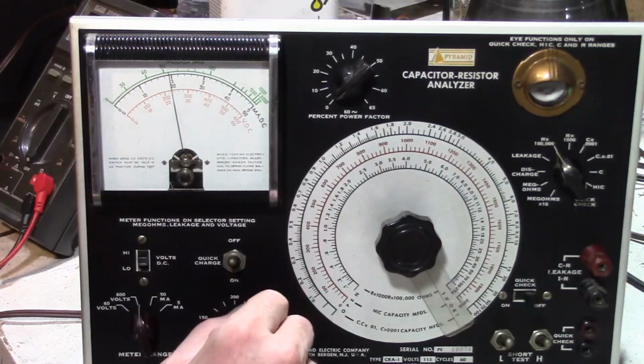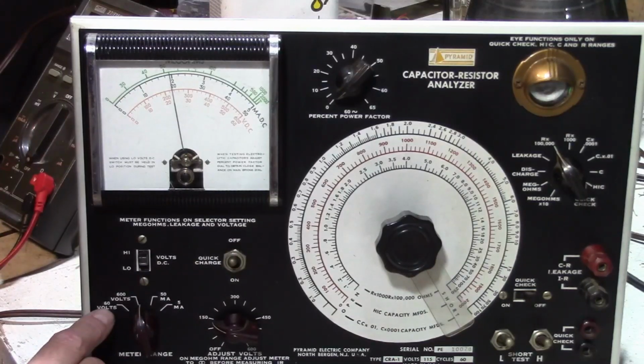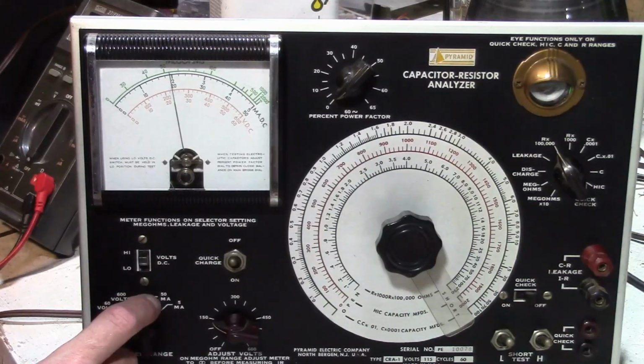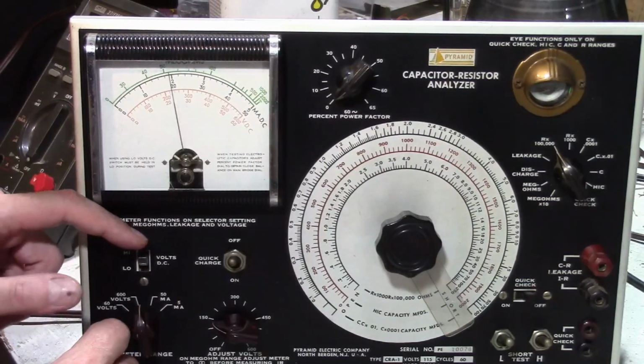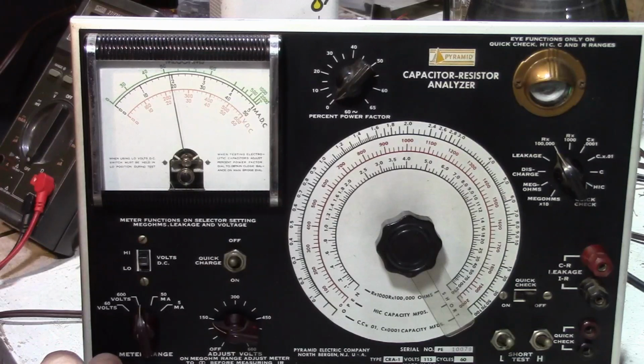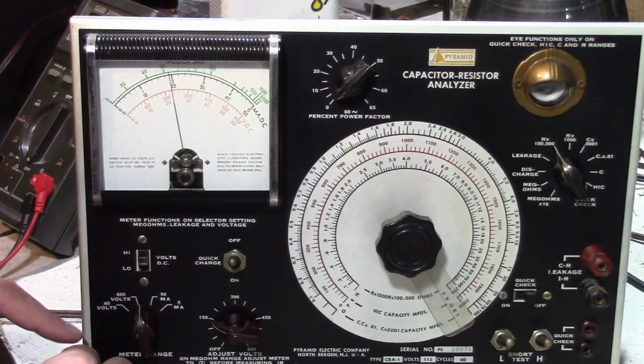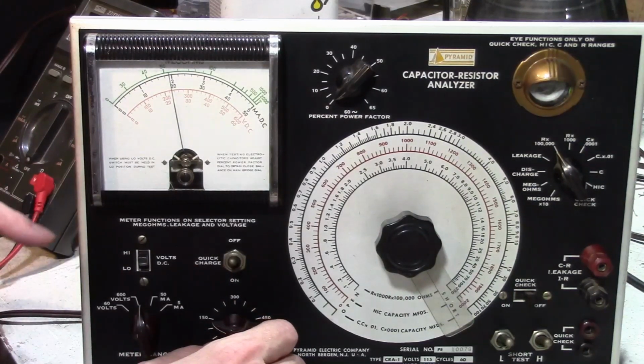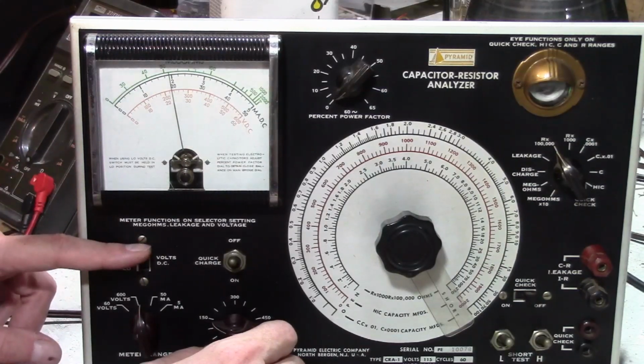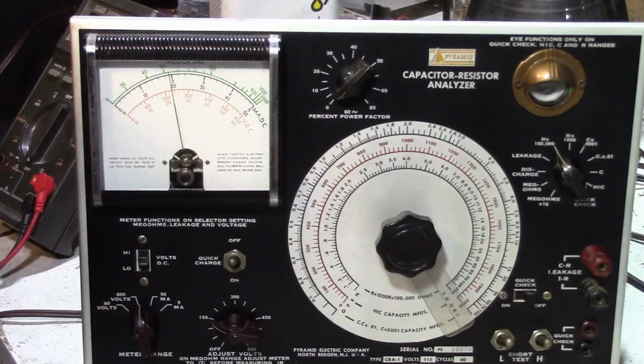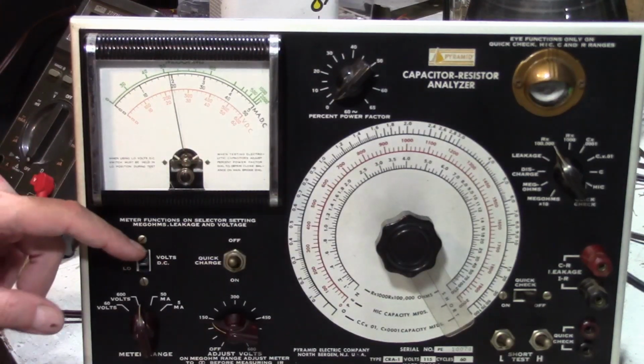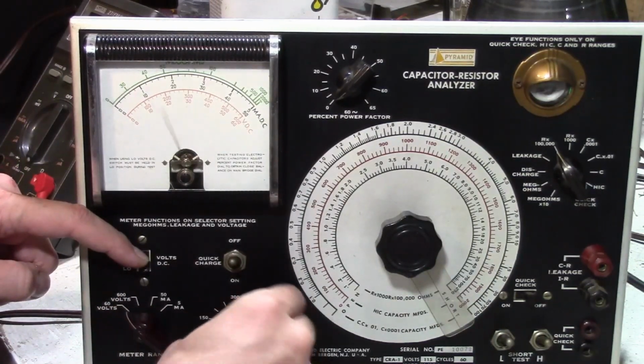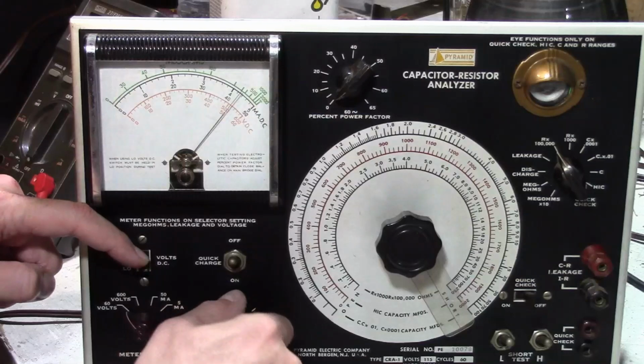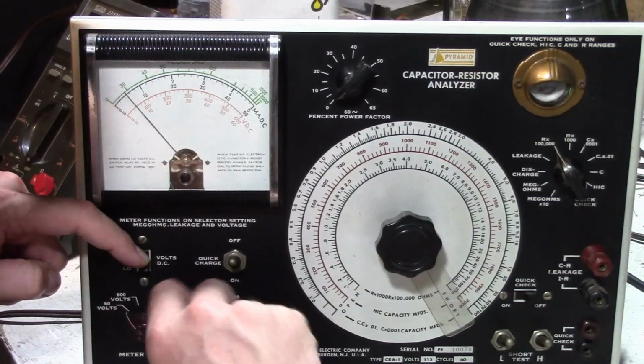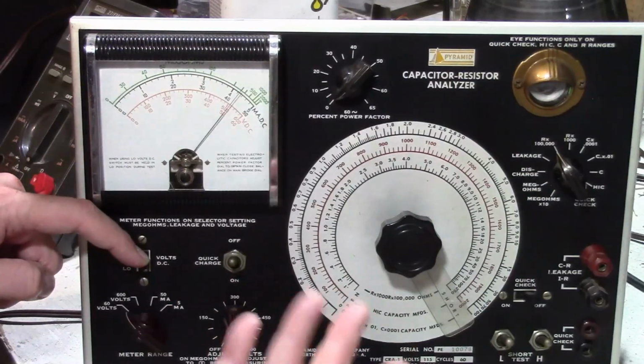I read the instructions more closely and I realized something, that when you're in the 60 volt range you're also supposed to flip this switch from high to low DC, which is a little annoying because it's spring loaded. I'm guessing that's to prevent damage to the meter, so imagine if you had this thing cranked up and you flip from 60 to 600 and you didn't change the switch, you're going to really risk serious damage to that meter. But anyways, when we flip this to low, put this on 60, now we can adjust it. It doesn't quite make it up to 60, but it goes from about 5 to 60 volts. So this would be for testing lower voltage electrolytics.